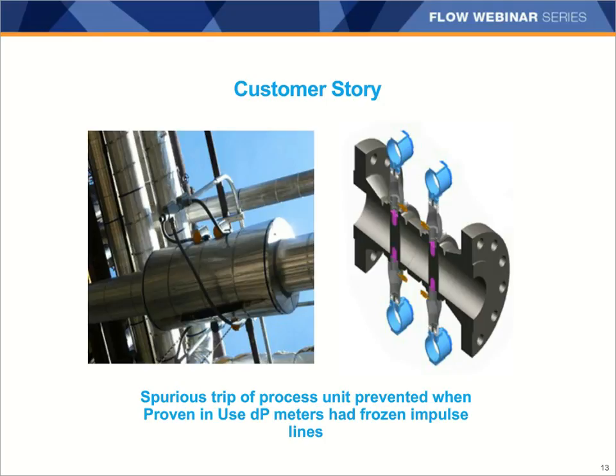They really wanted to use vortex meters for the application because the alternative DP meters required a lot of heat tracing of the impulse lines. They had more potential leak points, and they had a potential for impulse line freezing and plugging. And they also provided less rangeability than this particular application required. The quad vortex would have been ideal for the application and would have provided all 4 measurement points.